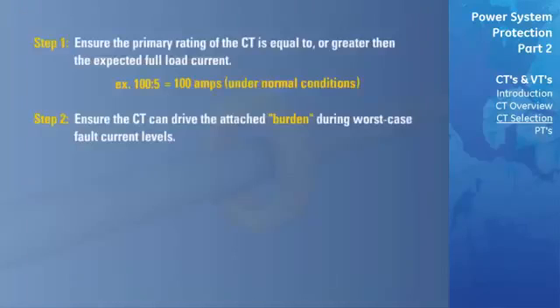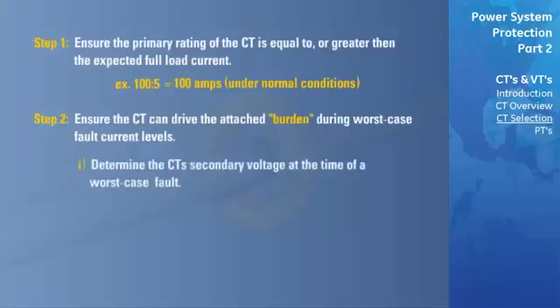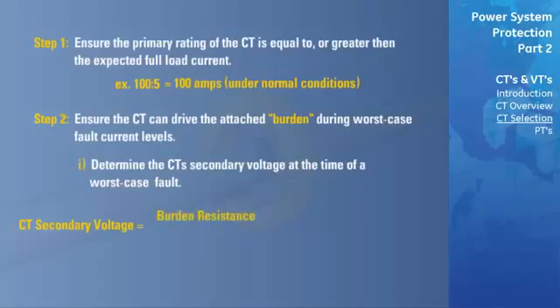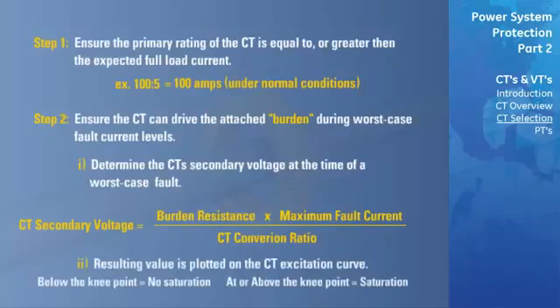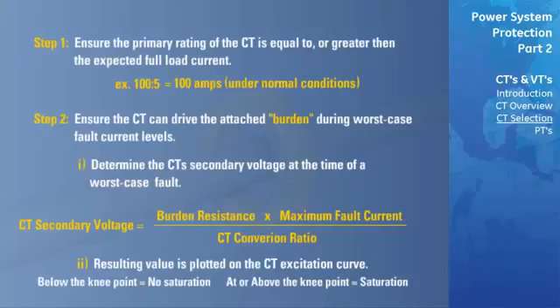To determine whether the CT can drive the attached burden under worst-case fault conditions without saturating, we must determine what the CT's secondary voltage will be at the time of this fault. The CT secondary voltage at the time of fault is equal to the burden resistance times the maximum fault current divided by the CT conversion ratio. The resulting value is then plotted onto the CT excitation curve. If the value plotted on the curve is below the knee point, then the CT will not saturate. If the value is equal to or greater than the knee point, then the CT will saturate.